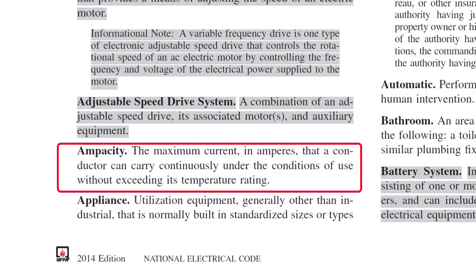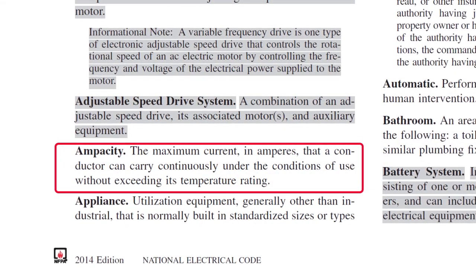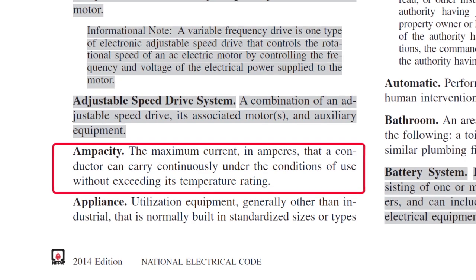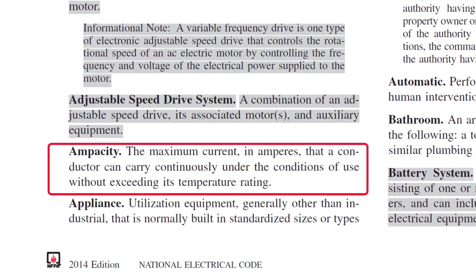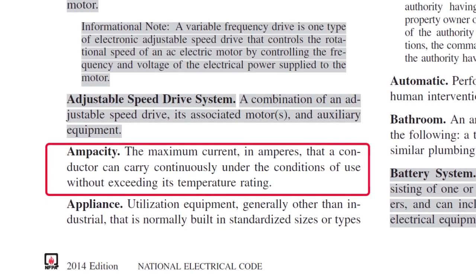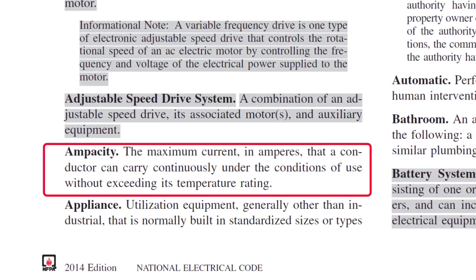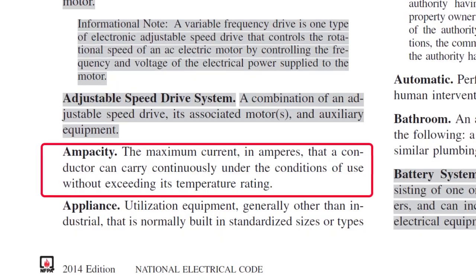Well, the term ampacity was actually coined by the National Electrical Code, I don't remember how many years ago, well before my time. Ampacity is the maximum current in amperes that a conductor can carry continuously under the conditions of use without exceeding its temperature rating. So it's really a temperature requirement, even though it's based in amperage. Thus, the subject of what we're talking about, how temperature ties into this.